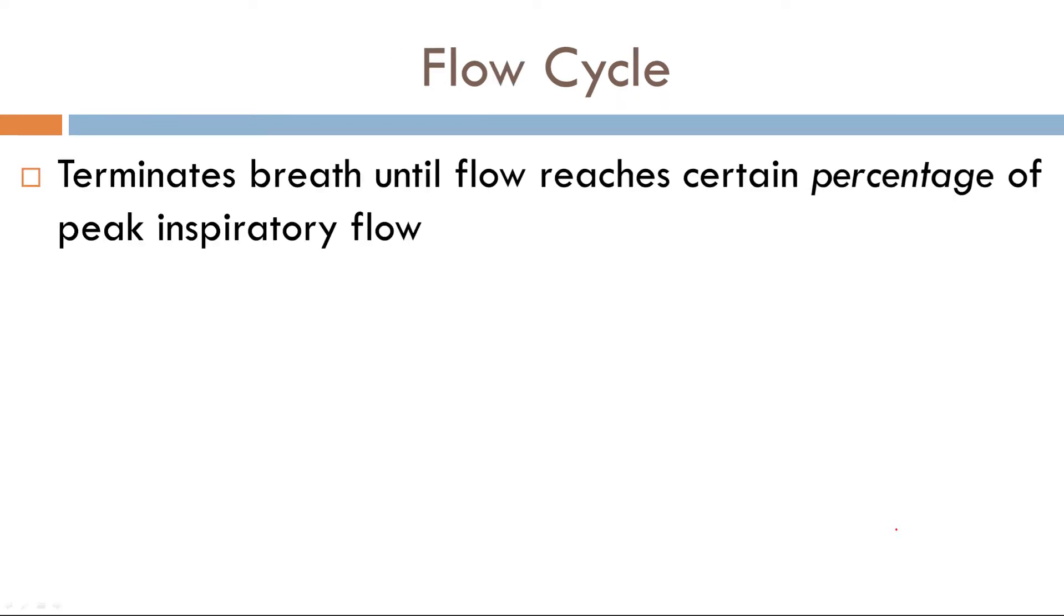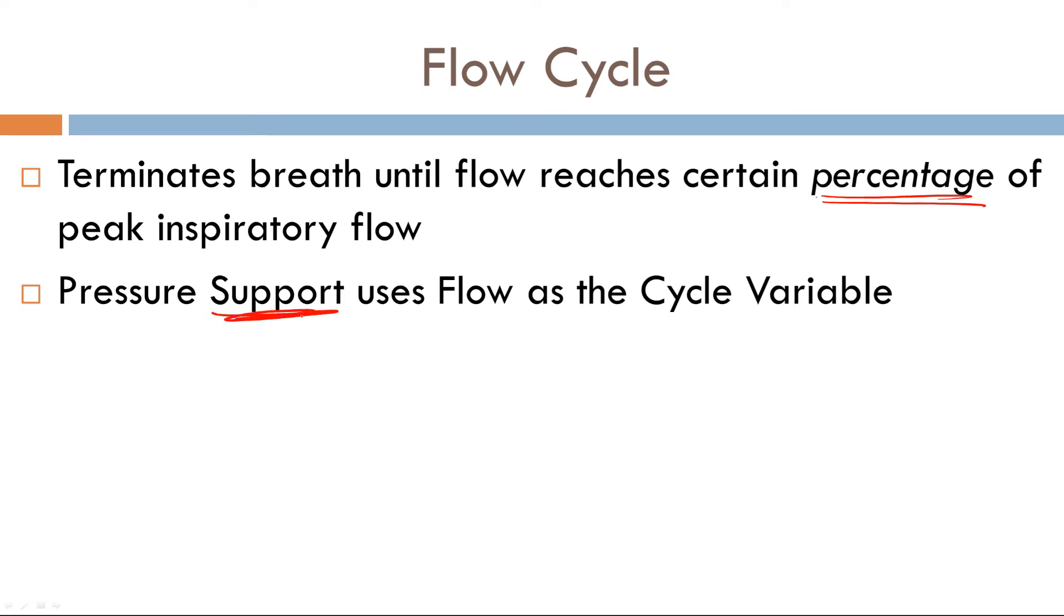Now flow cycle, this is the one that's a little bit more involved. Let's discuss it. Here's a definition. The vent will continue to deliver a breath until the flow reaches a certain percentage of the peak inspiratory flow. Now what mode of ventilation uses flow as the cycle variable? Pressure support, not pressure control. Pressure support ventilation uses flow as a cycle variable.